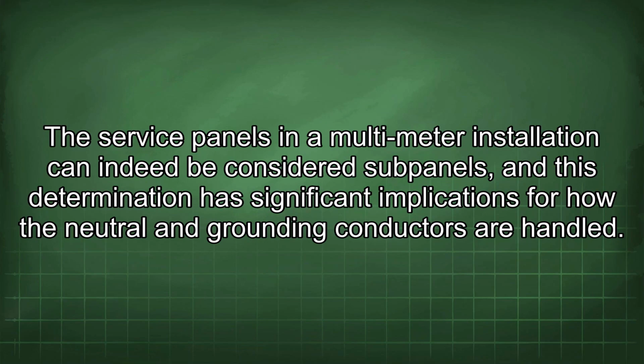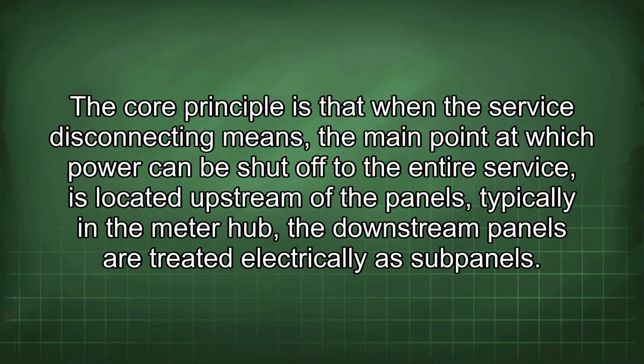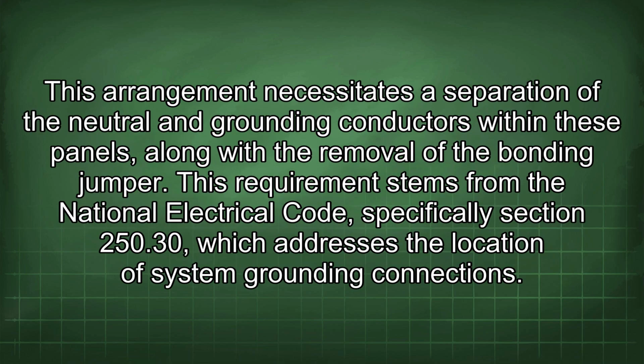The service panels in a multimeter installation can indeed be considered subpanels, and this determination has significant implications for how the neutral and grounding conductors are handled. The core principle is that when the service disconnecting means, the main point at which power can be shut off to the entire service, is located upstream of the panels, typically in the meter hub, the downstream panels are treated electrically as subpanels. This arrangement necessitates a separation of the neutral and grounding conductors within these panels, along with the removal of the bonding jumper.